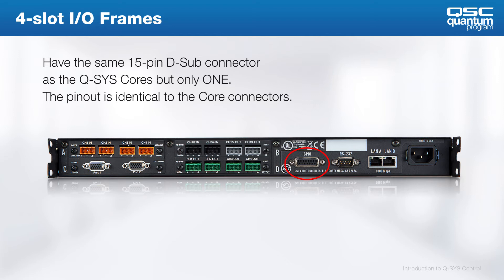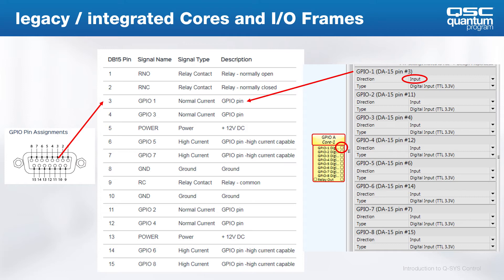Our I/O frame has the same DA15 as the 510i located here. If you look in Q-SYS Designer in the control properties for a device, you have a list of pin assignments and their corresponding functionality. Here we have GPIO 1 on pin number 3, configured as a digital input. This signal would enter your schematic on the right side of the GPIO component.